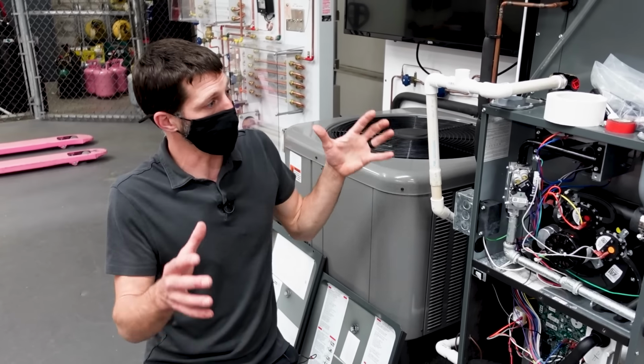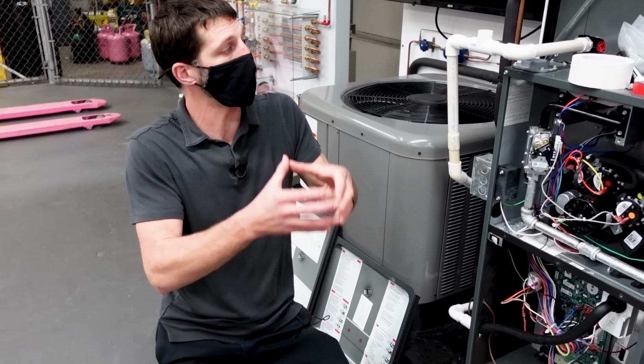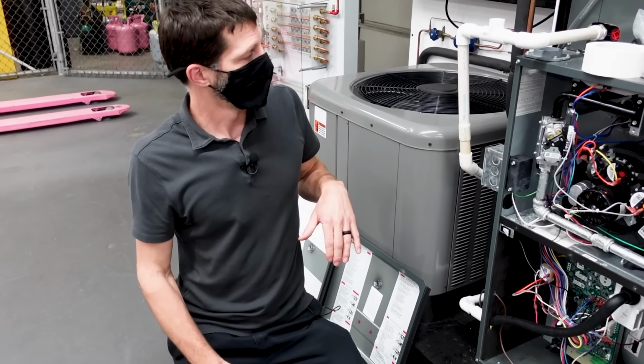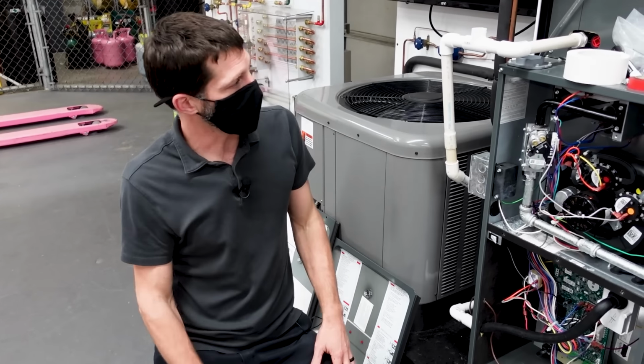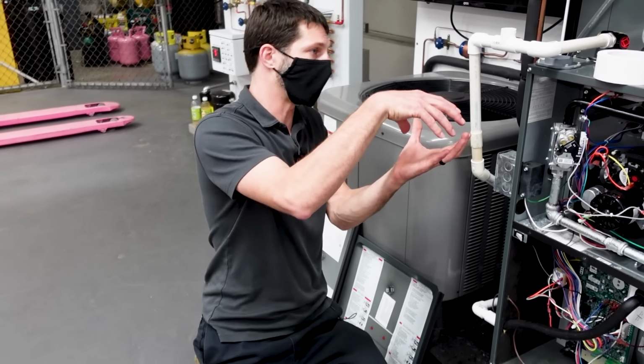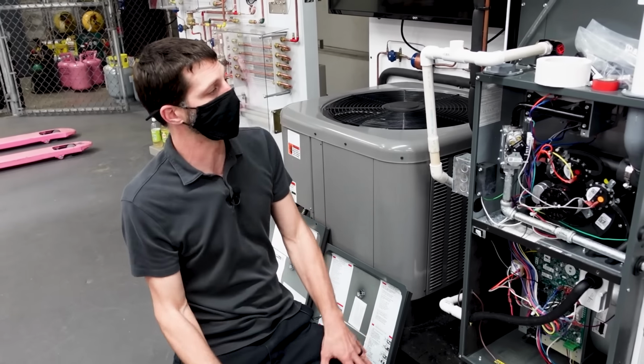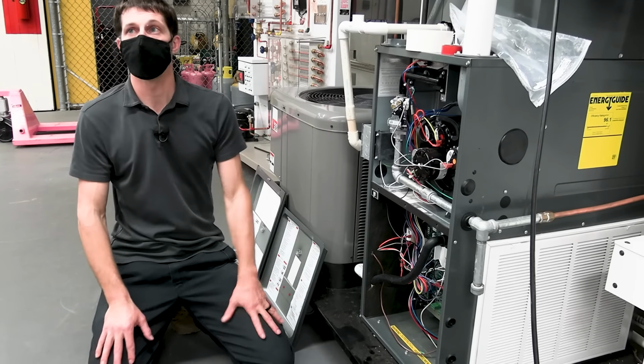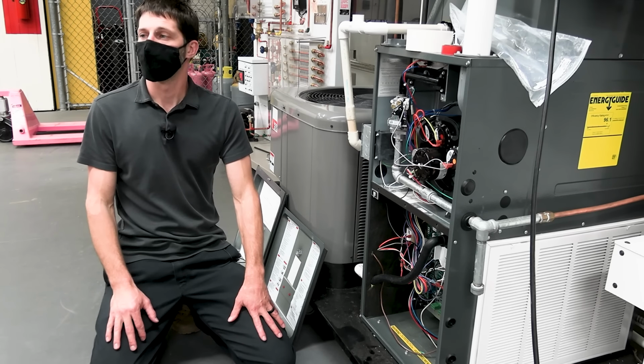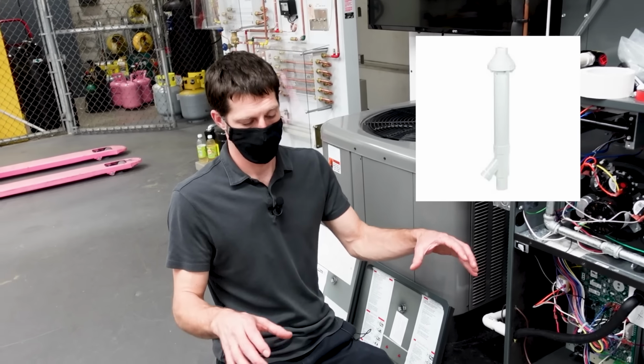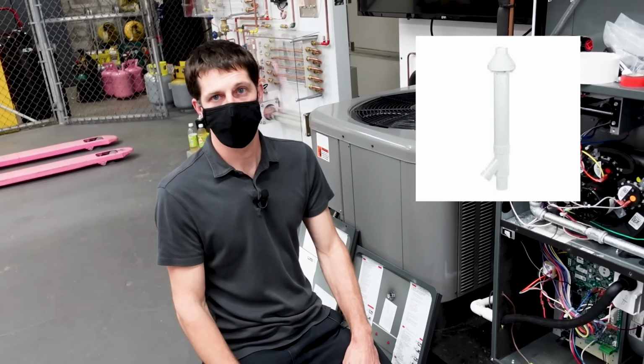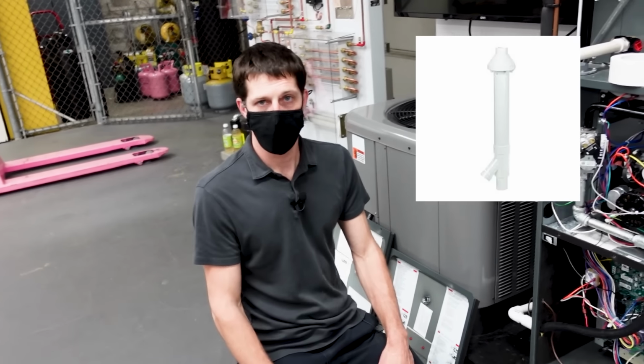Me personally, I like to go into a concentric kit, so there's one hole out of the building instead of two. And it just makes for a nice, neat installation, whether that concentric kit goes out through an exterior sidewall or through the roof. Yeah, and a concentric kit is just a tube within a tube. So you have a tube on the outside and then a smaller tube on the inside, and that way you don't have to make two penetrations, one for intake, one for outlet.